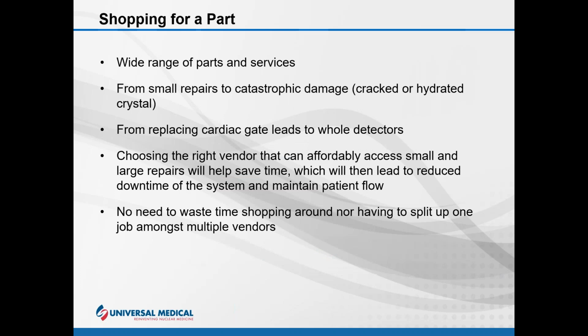Let's move into shopping for a part. Now that we know that we do need something, tech support has given us what we need and possibly to replace to repair our system. And with the previous info we spoke about so far, you should have the info you need to contact the vendor of your choice, and know the level of the vendor you're dealing with. What are their ranges of service? Can they deal with small peripherals that are constantly being changed out, or major catastrophes such as having to replace a complete detector? Choosing the right vendor that can affordably assess small and large repairs will help save time, which will lead to reduced downtime and help maintain patient flow.